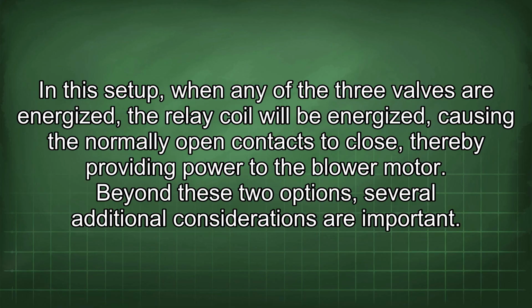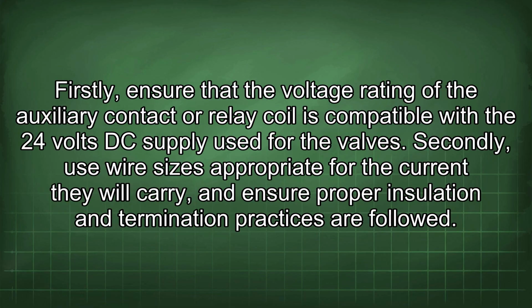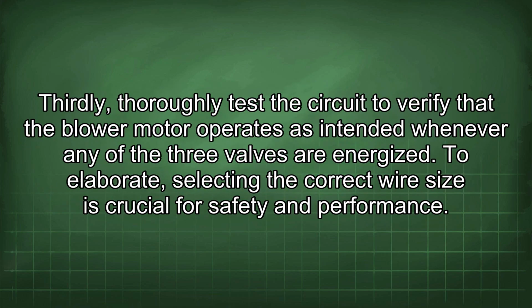Beyond these two options, several additional considerations are important. Firstly, ensure that the voltage rating of the auxiliary contact or relay coil is compatible with the 24 volts DC supply used for the valves. Secondly, use wire sizes appropriate for the current they will carry, and ensure proper insulation and termination practices are followed. Thirdly, thoroughly test the circuit to verify that the blower motor operates as intended whenever any of the three valves are energized. To elaborate, selecting the correct wire size is crucial for safety and performance.